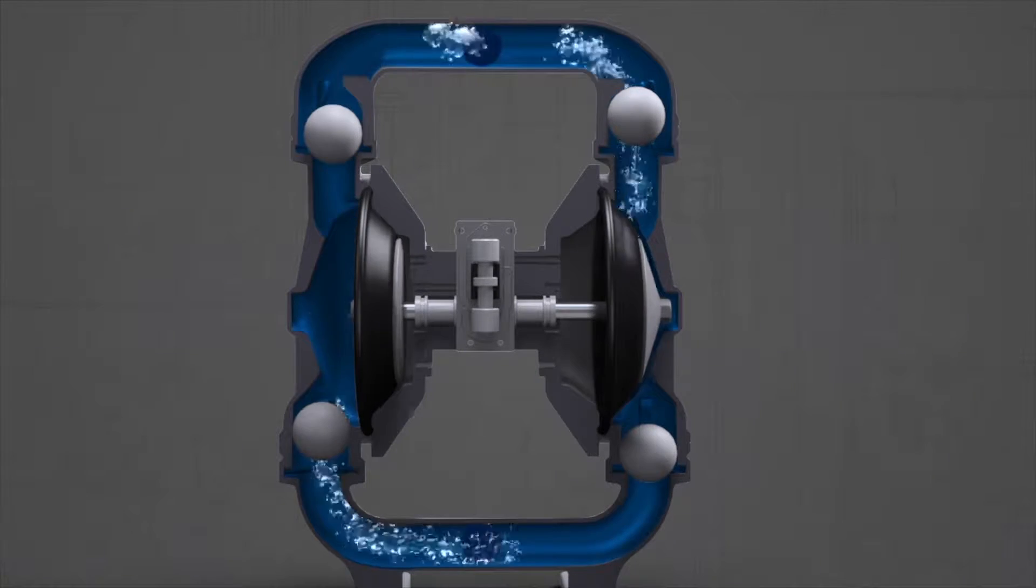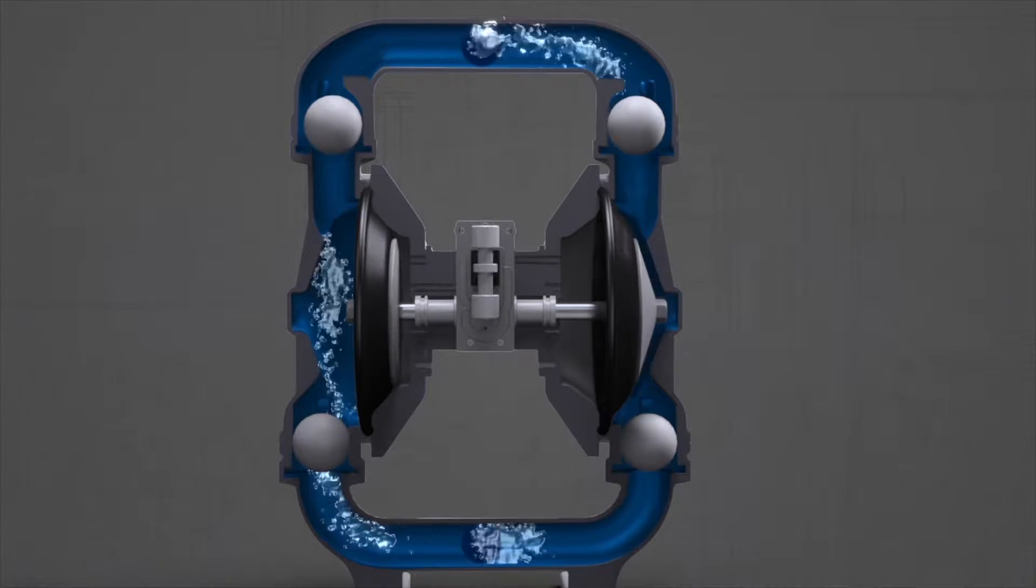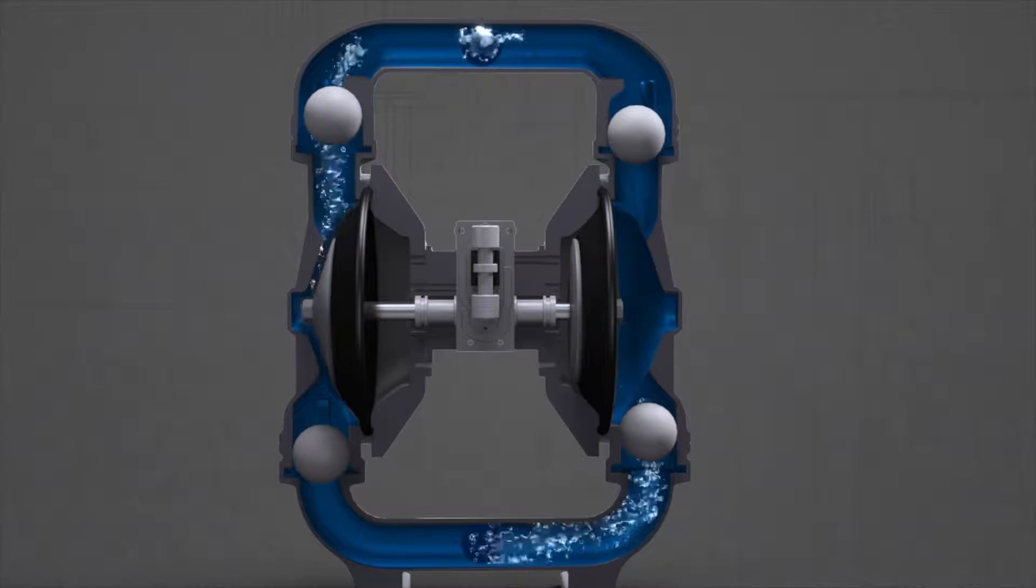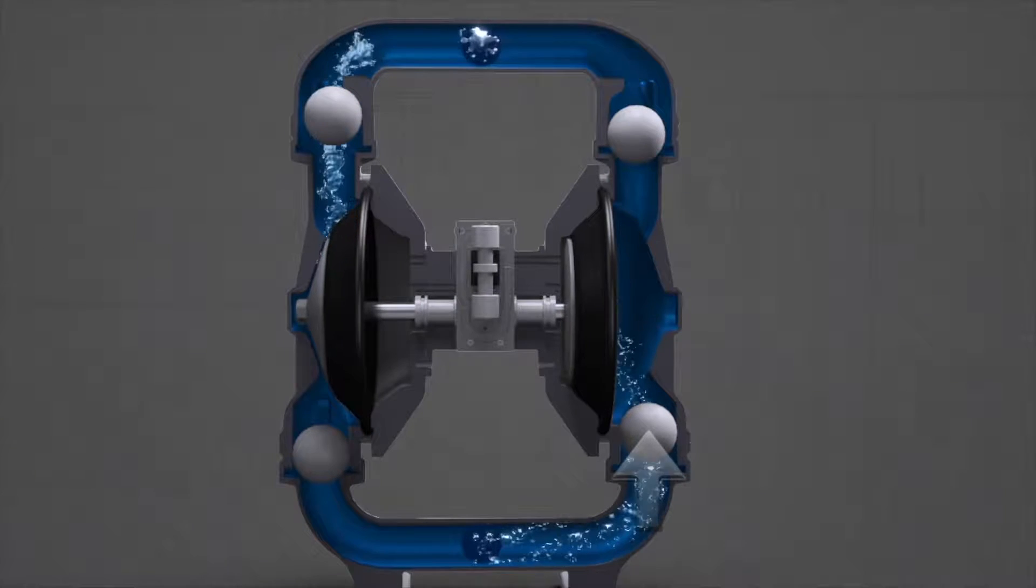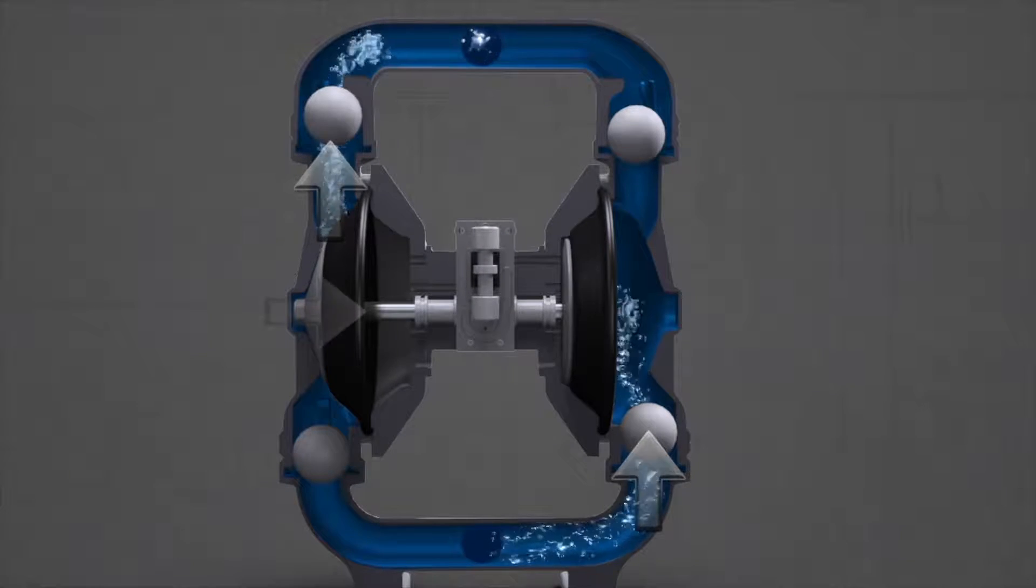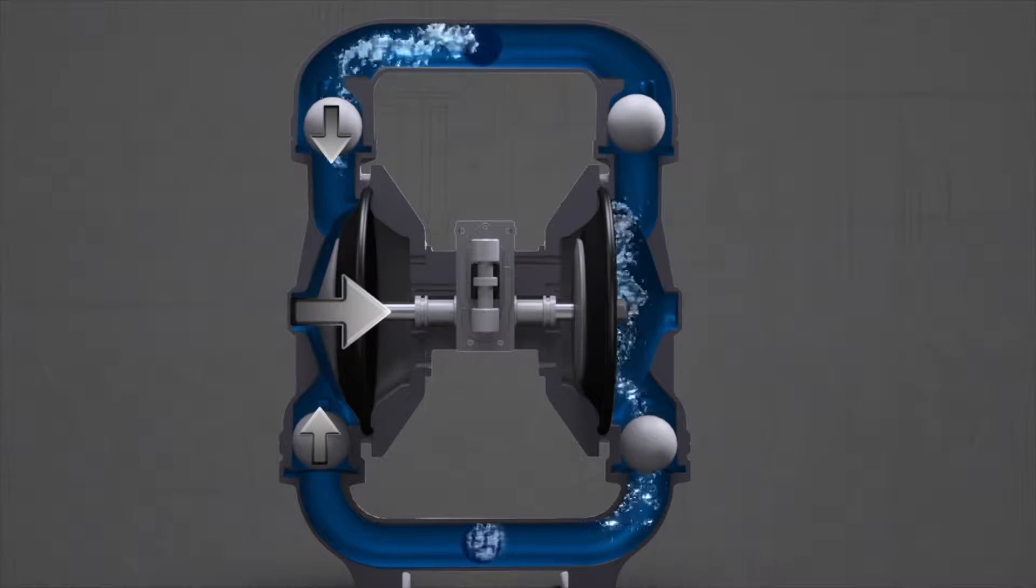Two diaphragms, connected by the diaphragm rod, work in unison to create the liquid motion of the pump. While one side is in suction mode, the other is in discharge mode. As a diaphragm moves inward, it creates suction.